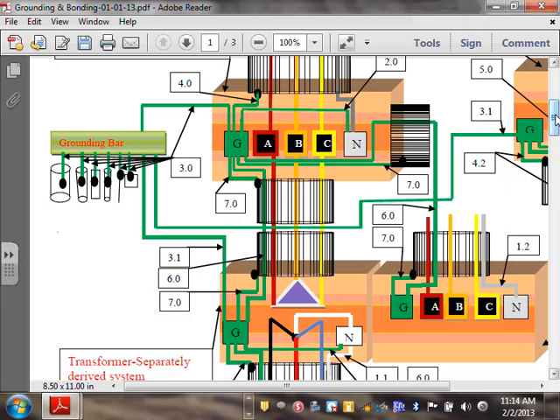Okay, in a transformer, you really have no option. You have no option of tying this neutral to the neutral here. No option. You cannot tie them. Like you asked me, you can't tie this neutral and this neutral. These are apples and oranges. You can't tie the two neutrals together. So you really have no option other than becoming a separate derived system. Another place, guys, is a UPS system, uninterruptible power supply. You can run it as a separate derived system. Solar photovoltaic system with the inverters. So every time you create a power system, you have the option of a separate derived system. Okay, now in this case, the notoriously famous one that all of us deal with is a transformer.